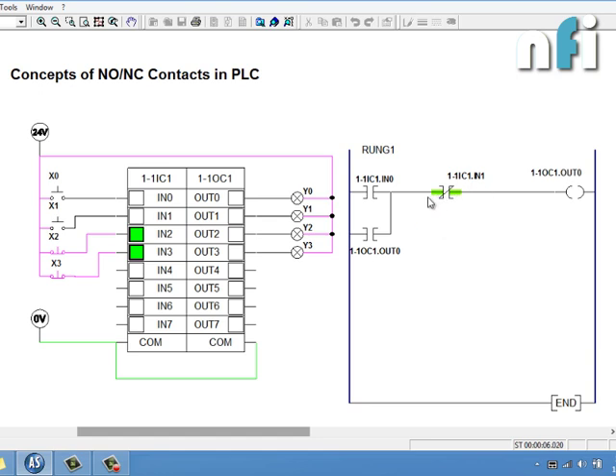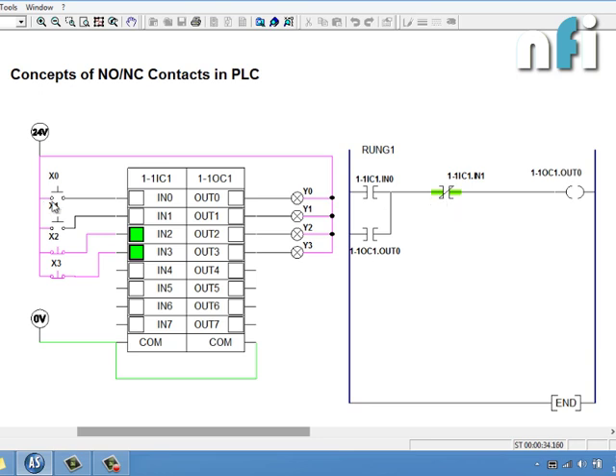There is a difference between a switch and a contact. This is a NO switch, this is an NC switch, this is a NO contact, and this is an NC contact. Contacts are those which are turned on and off by electromagnetic action or software modes inside a PLC or relay. NC and NO switches are physical switches; auxiliary contacts are also physical contacts on relays.